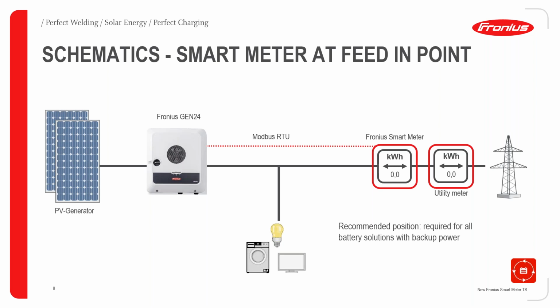If you look into the schematics of the smart meter, where do you position them? Normally we recommend right after the utility meter. When the electricity connection point at home is coming from the grid, there will be a meter, and then after that there will be some protections like fusing or other switches. Then right after these switches, please put this Fronius Smart Meter TS or Fronius Smart Meter, so that you will place them in the feed-in point. This is called the feed-in point.